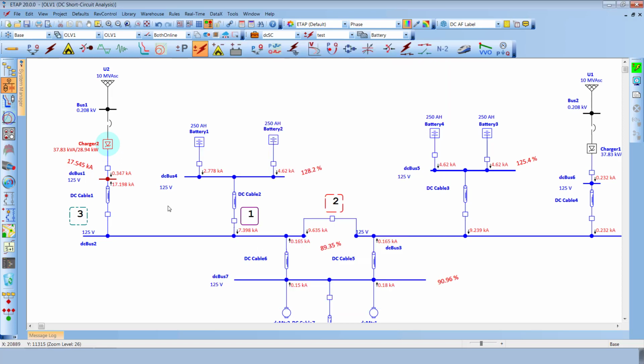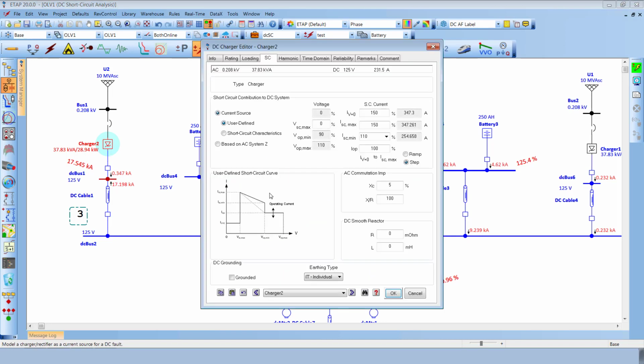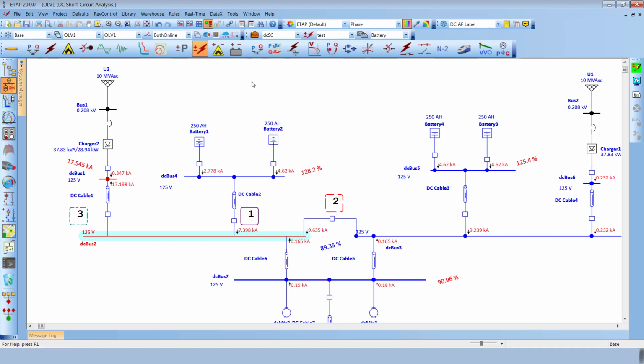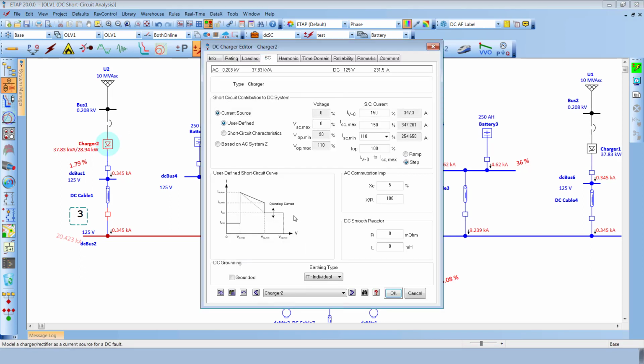Now as we move further away from the charger as a source to the downstream, the terminal voltage at DC bus 1 starts to increase based on the user-defined short circuit curve as shown in here. So when the bus 2 is faulted, the actual contribution of the chargers is based on 1.79% of the bus terminal voltage, which in this case is in between the ISC minimum and ISC maximum.